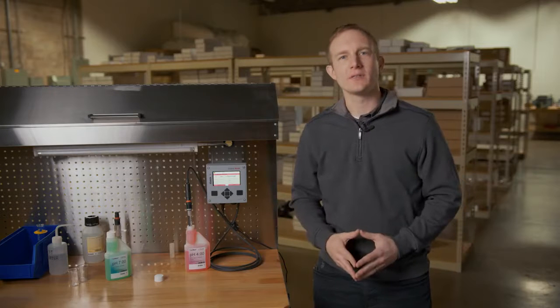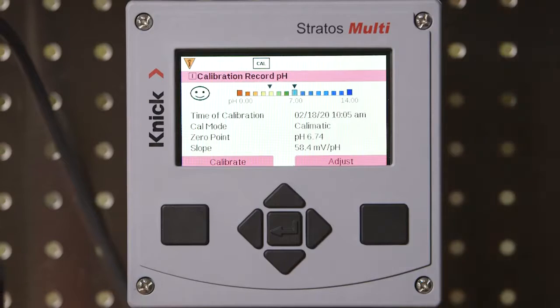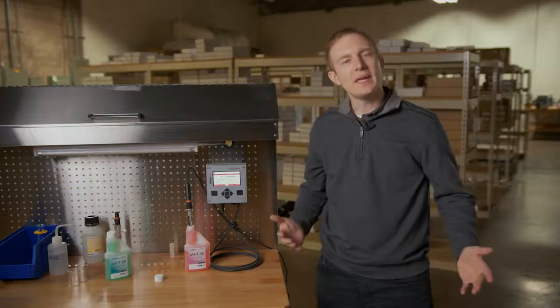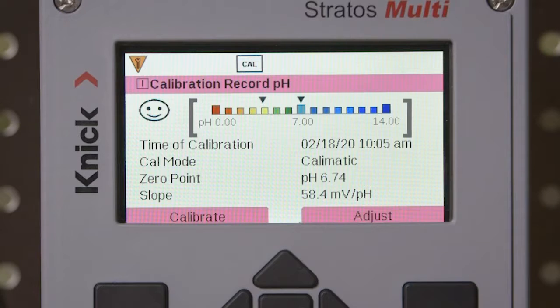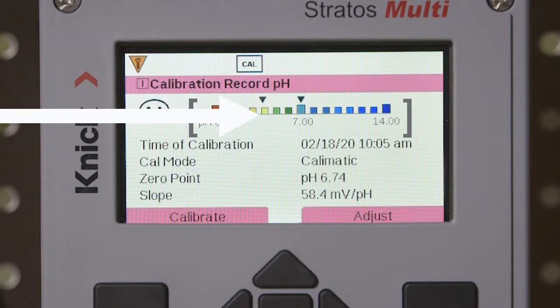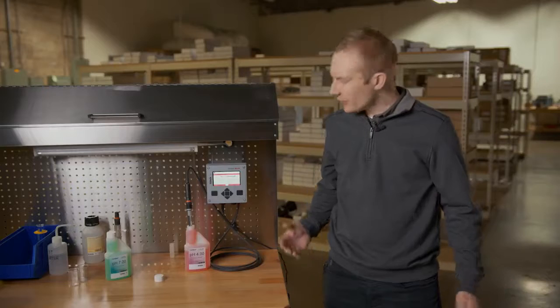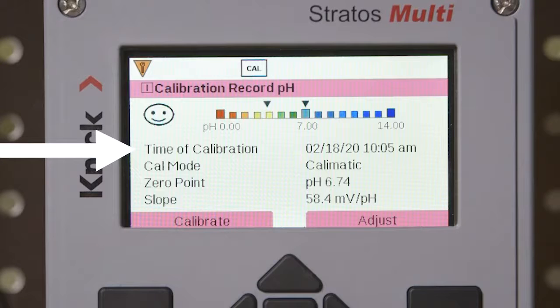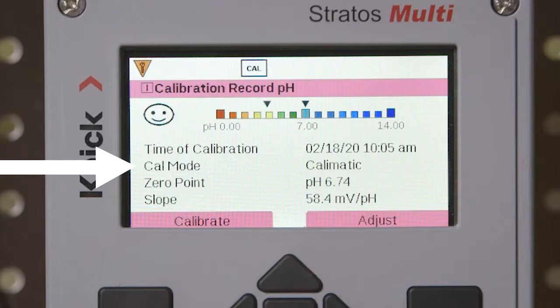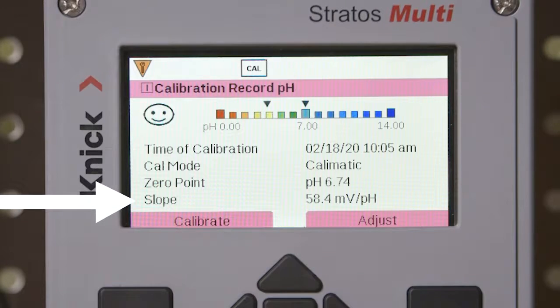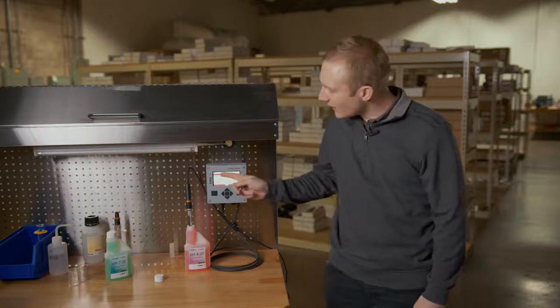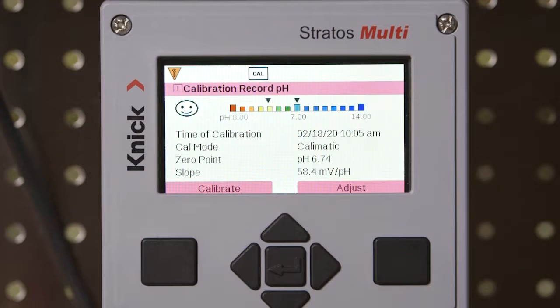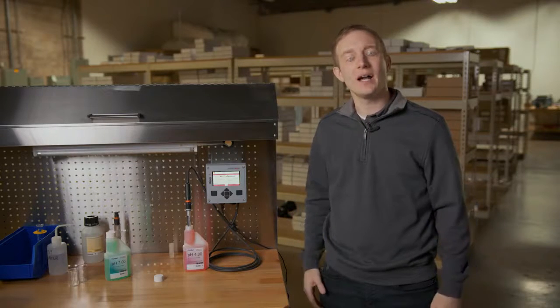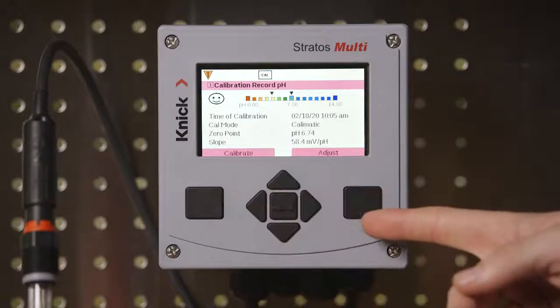Once complete in the second buffer solution, our Stratos Multi now displays the specifics of our calibration record. A pH chart at the top of the screen indicates the 2 buffer values that were used, 4 and 7. Next, we have a timestamp of our calibration, followed by the type of calibration that was performed, as well as the specific values of our 0 point and slope of our electrode. Lastly, we have the sensor face icon in the top left corner of our display, indicating the status of our calibration. Here you can see we have the opportunity to select either Calibrate or Adjust.